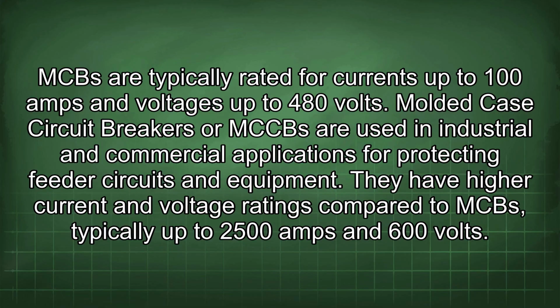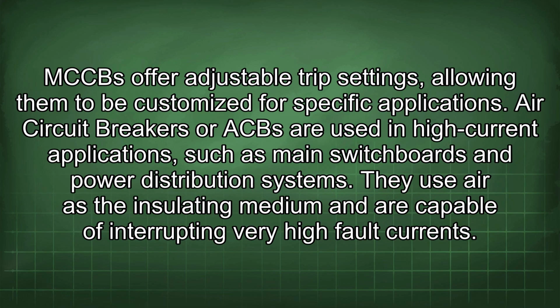Molded case circuit breakers, or MCCBs, are used in industrial and commercial applications for protecting feeder circuits and equipment. They have higher current and voltage ratings compared to MCBs, typically up to 2500 amps and 600 volts. MCCBs offer adjustable trip settings, allowing them to be customized for specific applications.